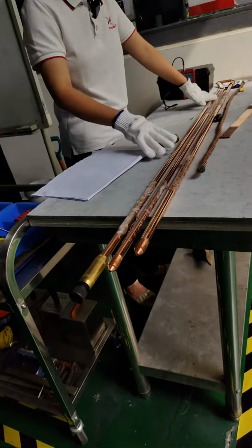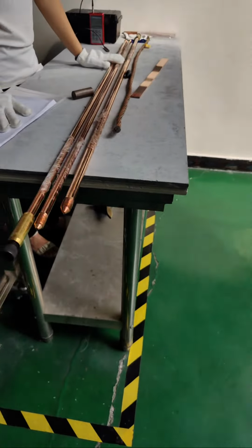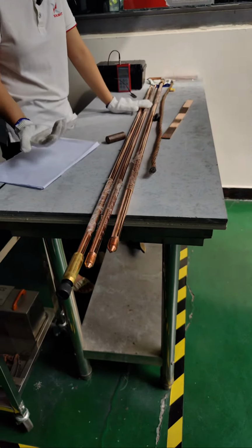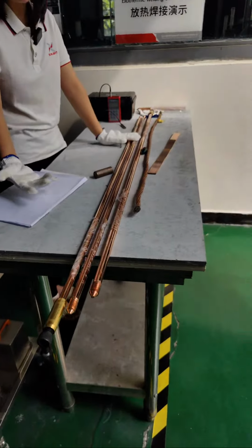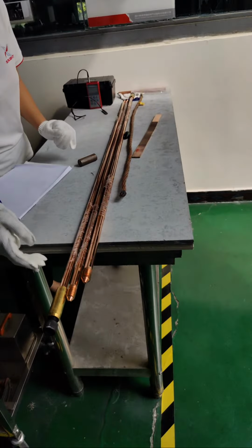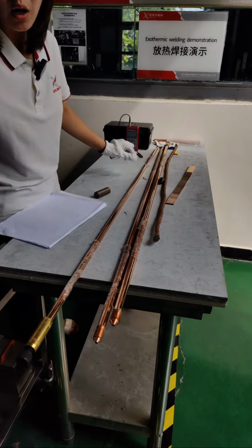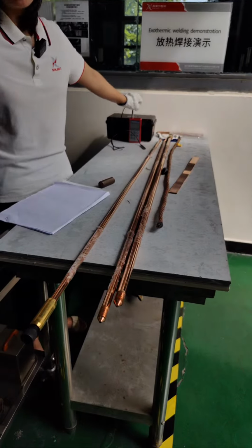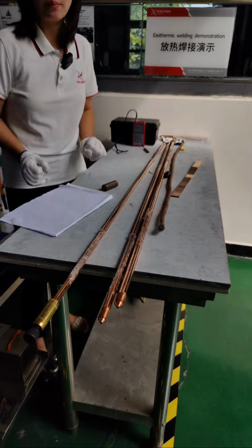You can send your requirements to our sales team and we can customize to your needs. We can offer them in half meter, 1 meter, 1.2 meter, 1.5 meter, 2 meter, or 2.2 meter lengths. You can also use a coupler to connect two earth rods together, which means you can have a 3 meter or 6 meter long earth rod for the earthing job.